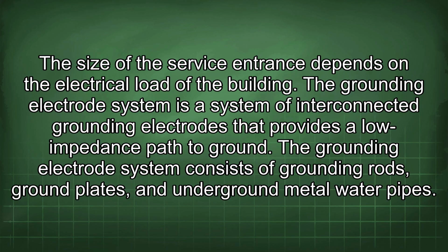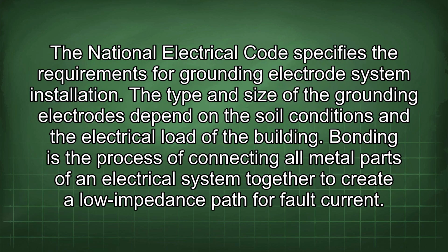The grounding electrode system is a system of interconnected grounding electrodes that provides a low impedance path to ground. The grounding electrode system consists of grounding rods, ground plates, and underground metal water pipes. The National Electrical Code specifies the requirements for grounding electrode system installation. The type and size of the grounding electrodes depend on the soil conditions and the electrical load of the building.